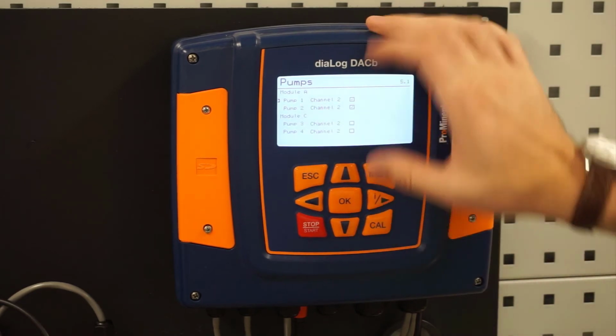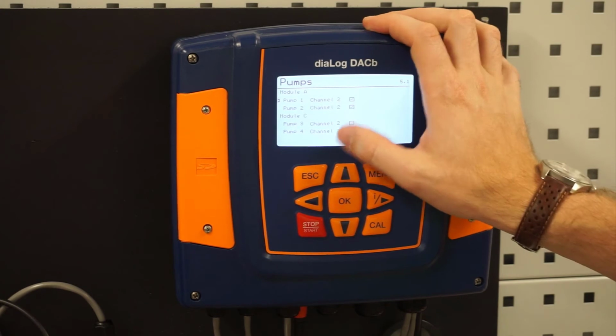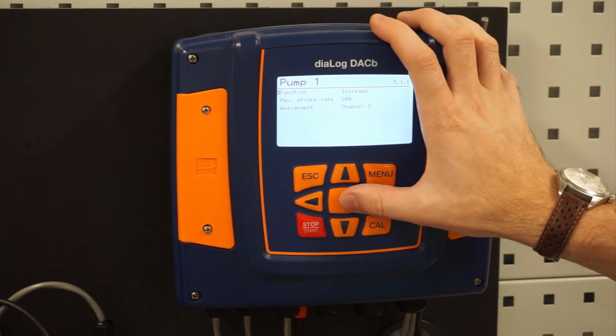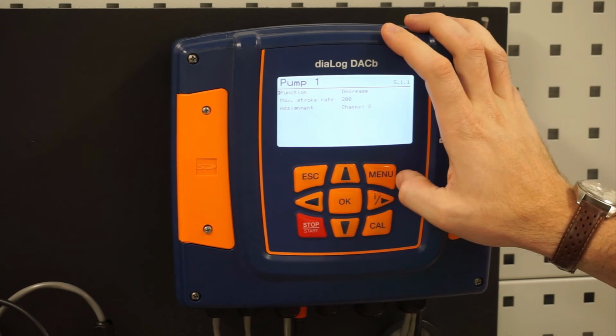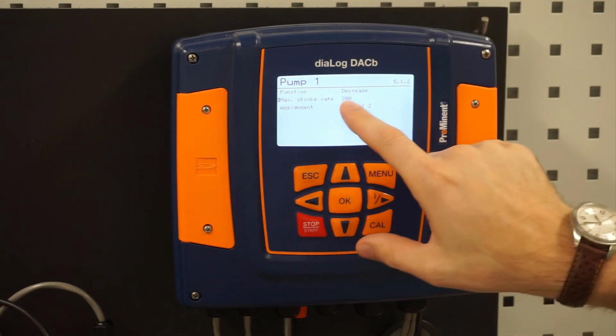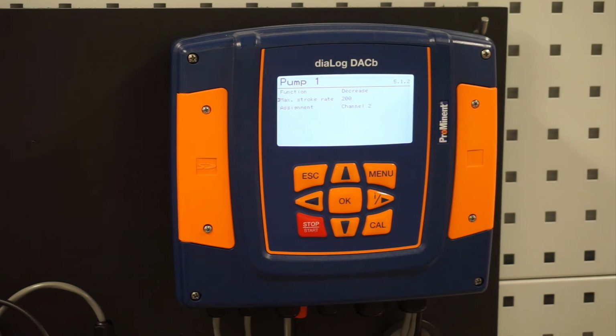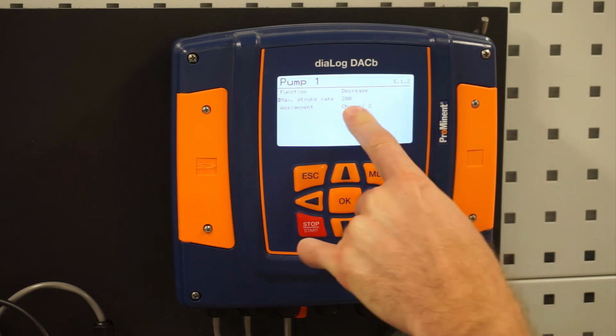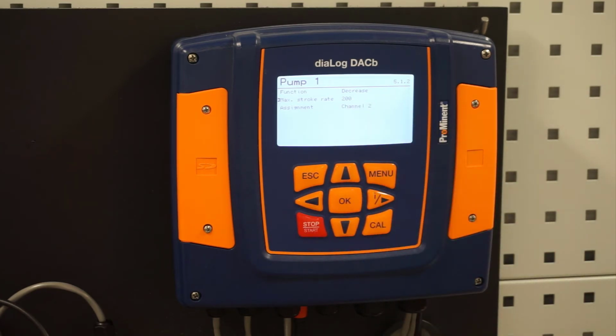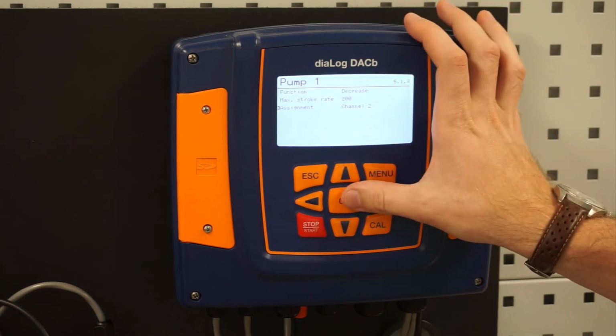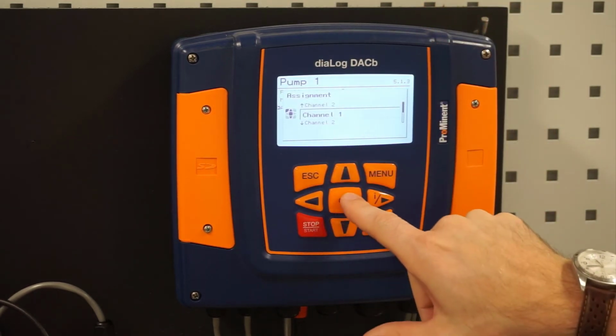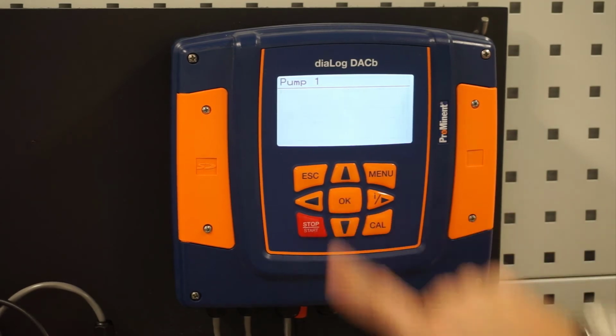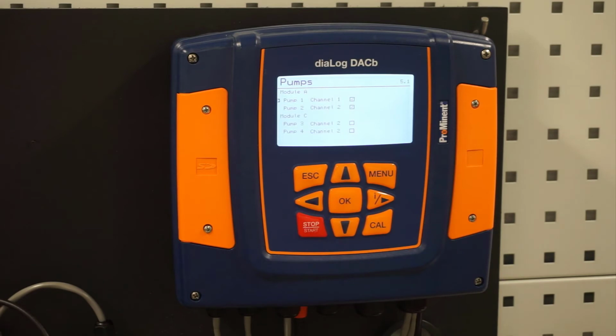For pump 1, let's say that is our acid pump for pH on channel 1. We can go in here. Putting in acid is going to decrease the pH. We would need to figure out what the max stroking rate of the pump is. We could also limit it. For instance, a gamma X has a max stroking rate of 200. Maybe it's oversized and I don't want it to ever get to that speed, so I could reduce that to 100 instead of 200. And then what assignment is it? We want it on channel 1 with our pH because it's our acid pump. We click that and we have that set up.